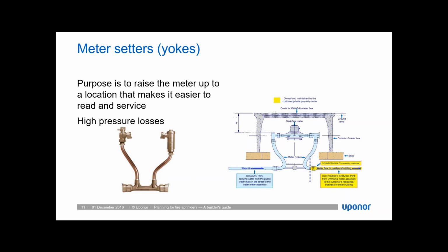The other difficult aspect of these meter setters is that the variation in the components and the sizes means there are no readily available published fixed losses for meter setters. The manufacturer can provide those losses at various flows, and often a water purveyor that uses these on all of their homes may have a standard assembly, but it is going to be important to obtain the information on that assembly so that it is incorporated into the design. Ideally, an alternative solution to a meter setter would be allowed, instead of one of these devices, which can have such a restrictive impact on your sprinkler system flow.